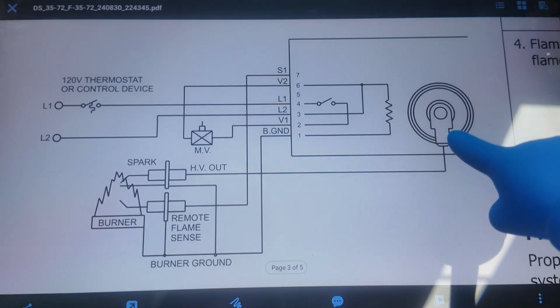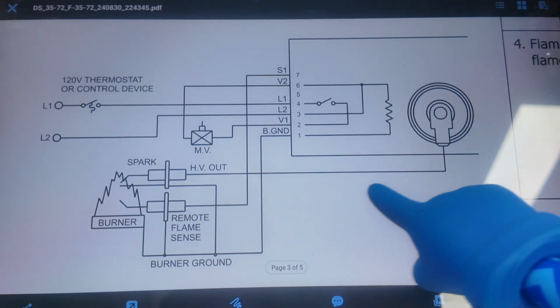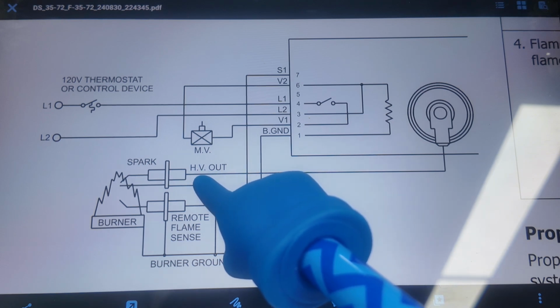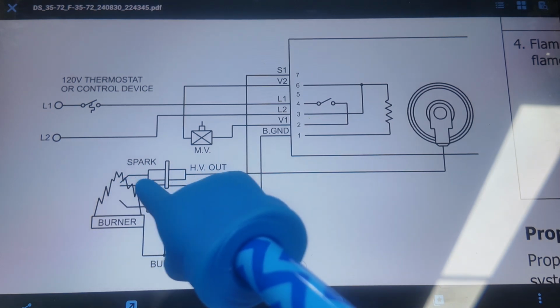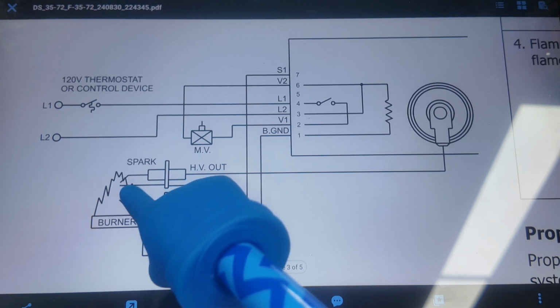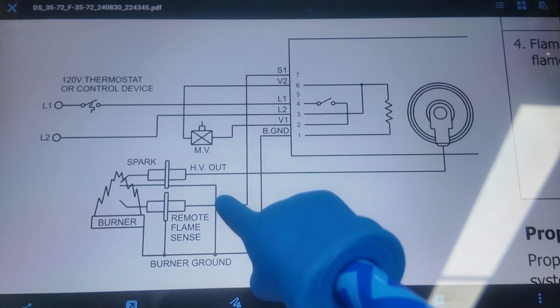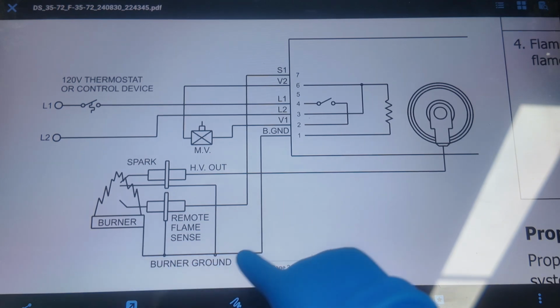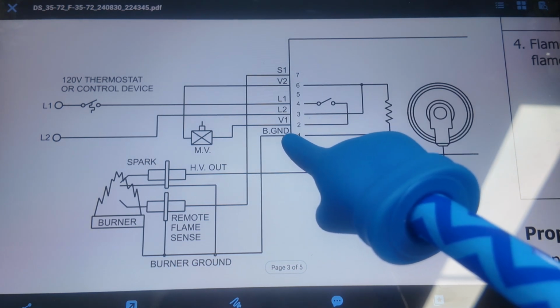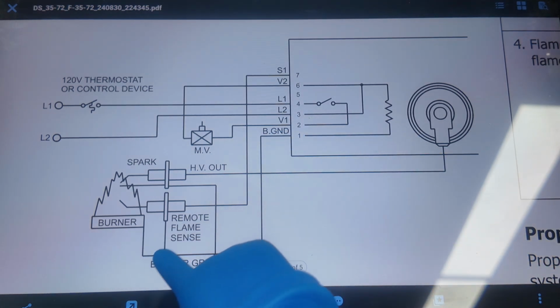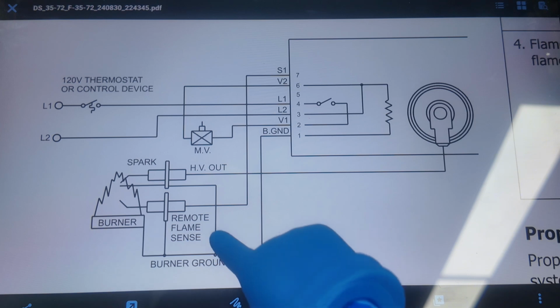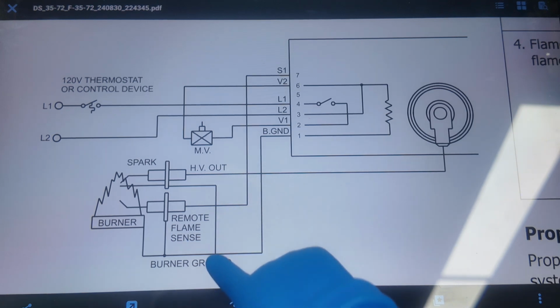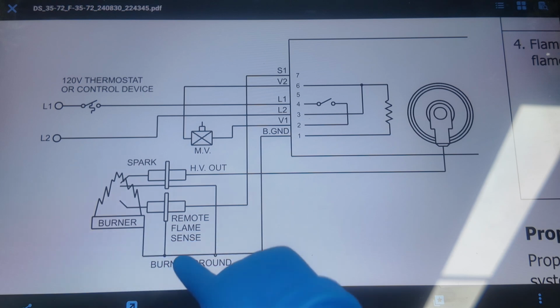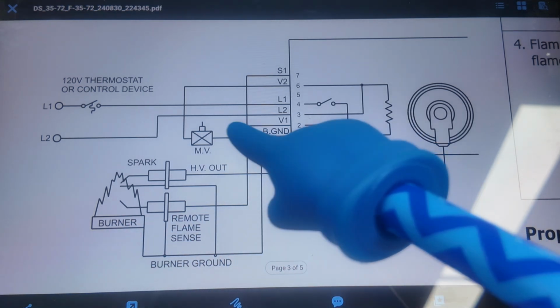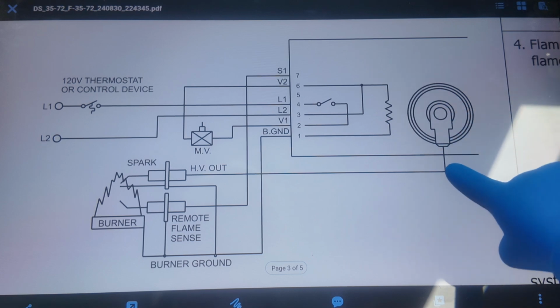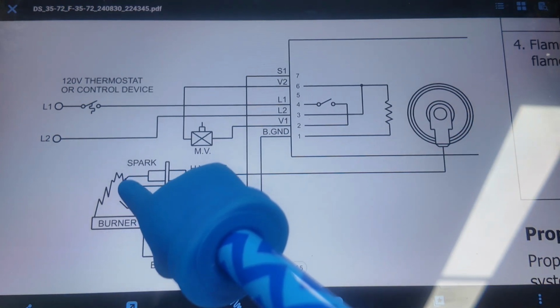igniter. So off this coil, we have a wire that comes out here. It's high voltage out. It goes out here and it's your ignition. Your other probe that arcs off comes back and is connected to the ground. And that all connects to burner ground, to B ground on the board. So B ground connects to your housing of your electrical panel, your igniter probe, and your burner itself. They all need to be bonded together. And then here we have the igniter, which goes and arcs off of ground.